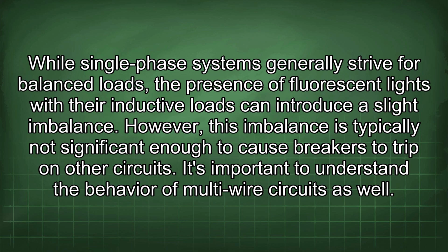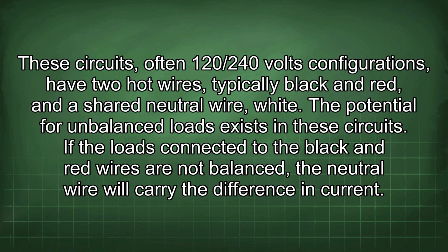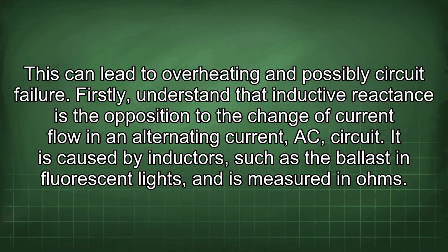It's important to understand the behavior of multi-wire circuits as well. These circuits, often 120/240 volts configurations, have two hot wires, typically black and red, and a shared neutral wire, white. The potential for unbalanced loads exists in these circuits. If the loads connected to the black and red wires are not balanced, the neutral wire will carry the difference in current. This can lead to overheating and possibly circuit failure.